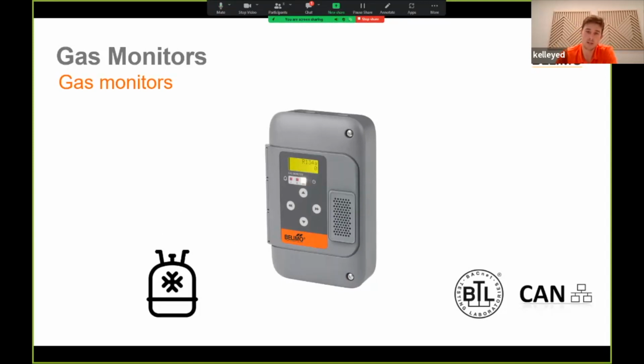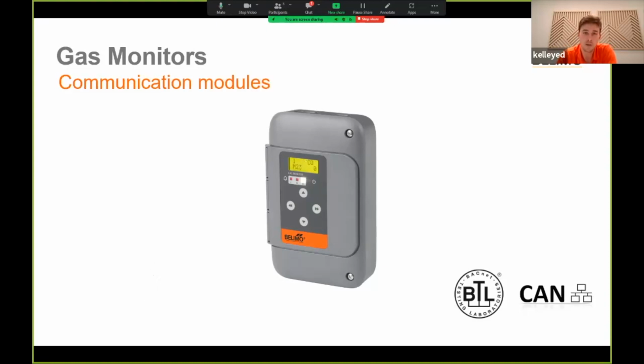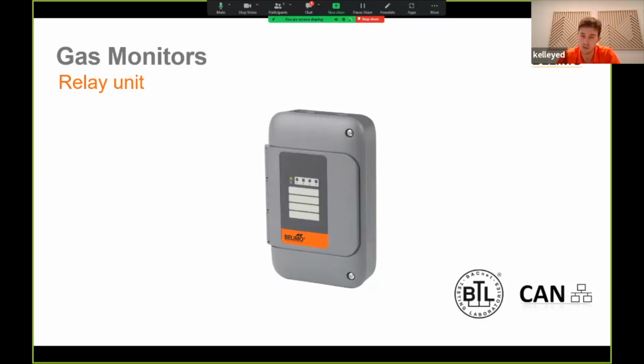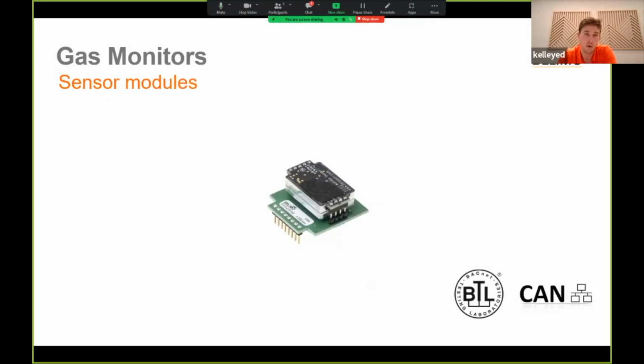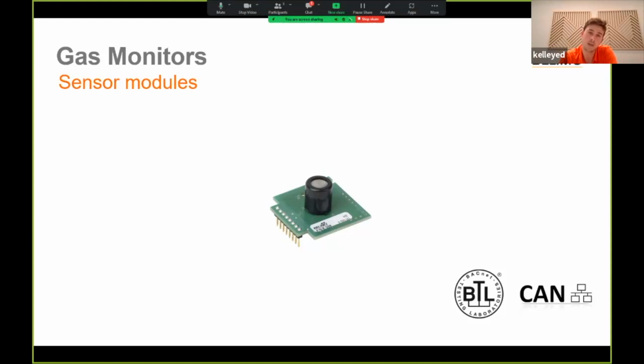So in addition to the four applications of gas monitors, we also have accessories too. So we have communication modules and relay units that allow for direct control from central locations. So the gas monitors physically control things directly through analog outputs and relays. But if you'd like to have something in a location that it's maybe more easily serviceable, these are where communication units and relay units can be used. Like we mentioned before, we have sensor modules that are factory calibrated and hot swappable. So when you replace them, you don't need to disconnect the unit from power and they're already pre-calibrated.